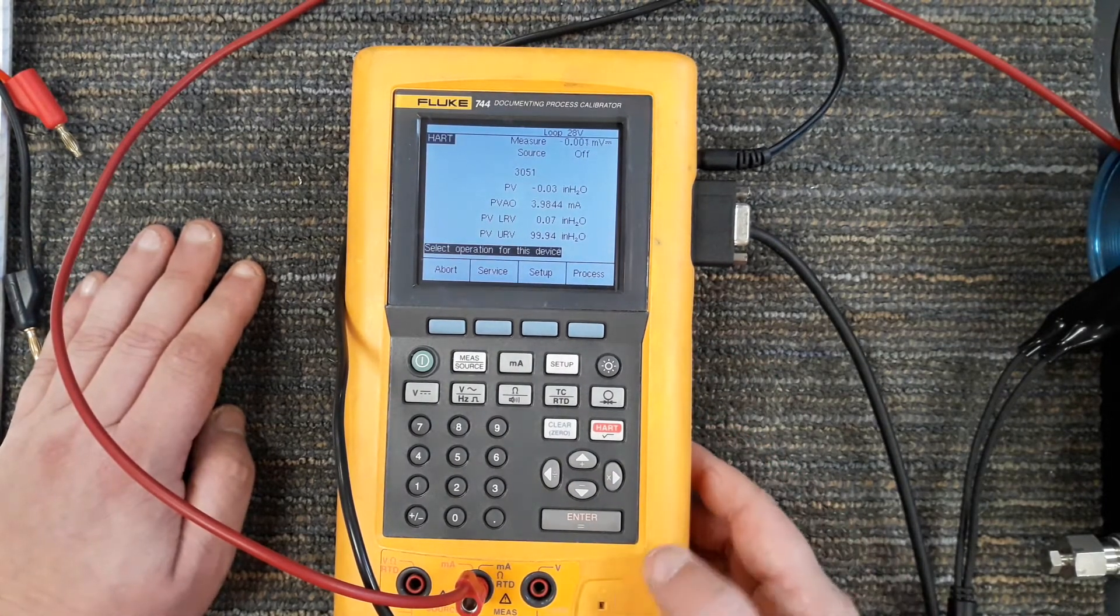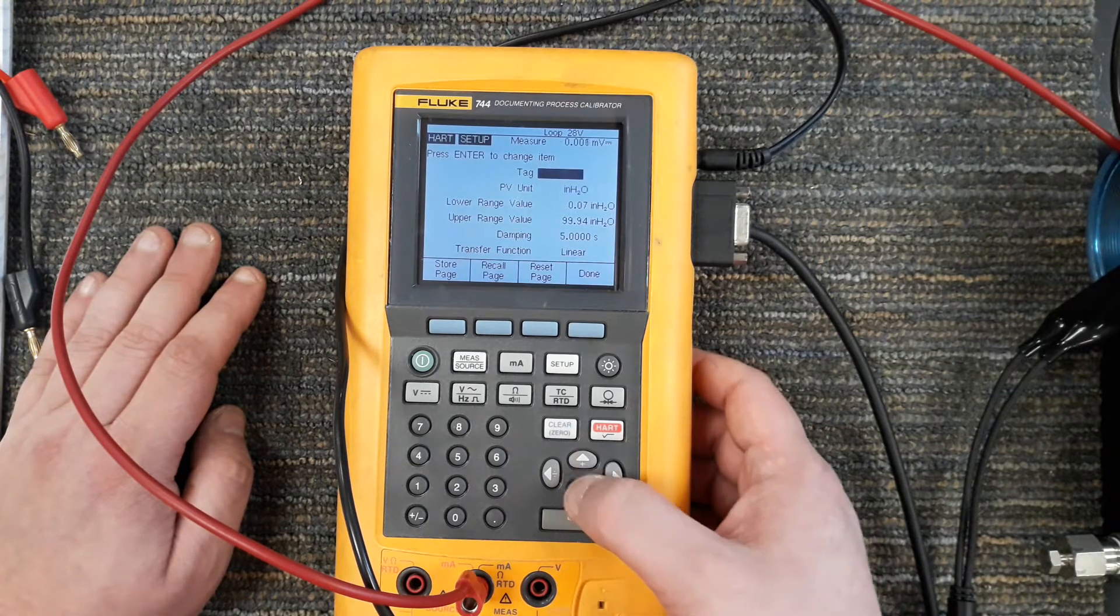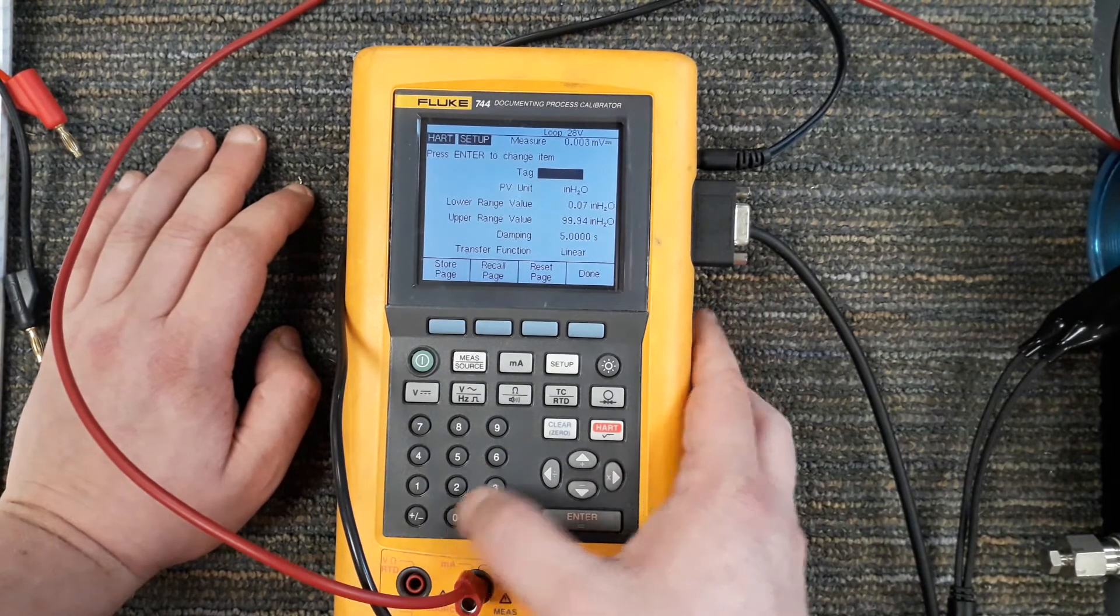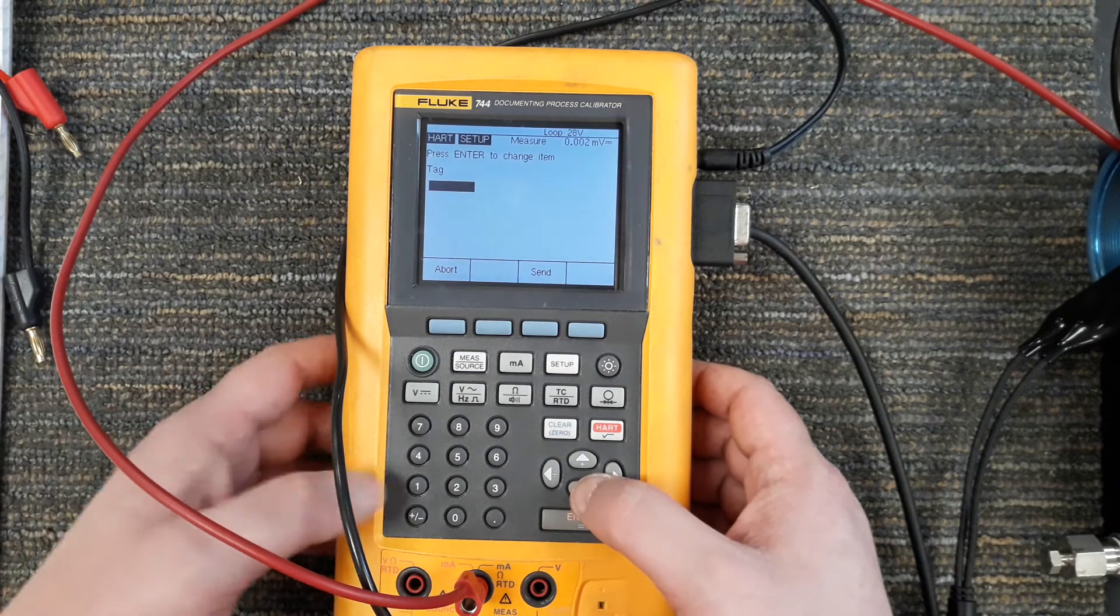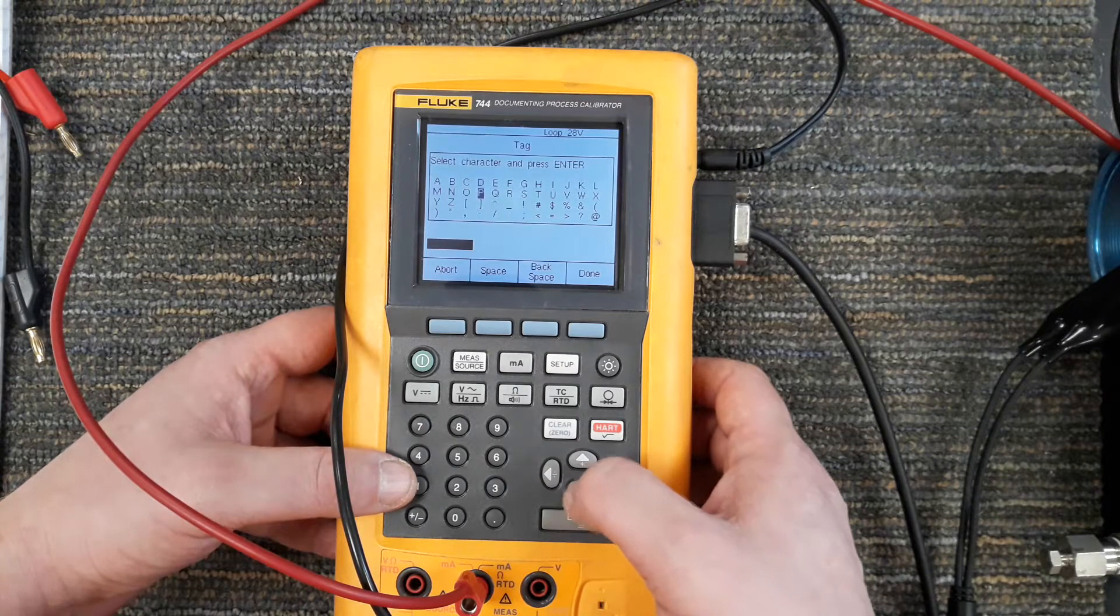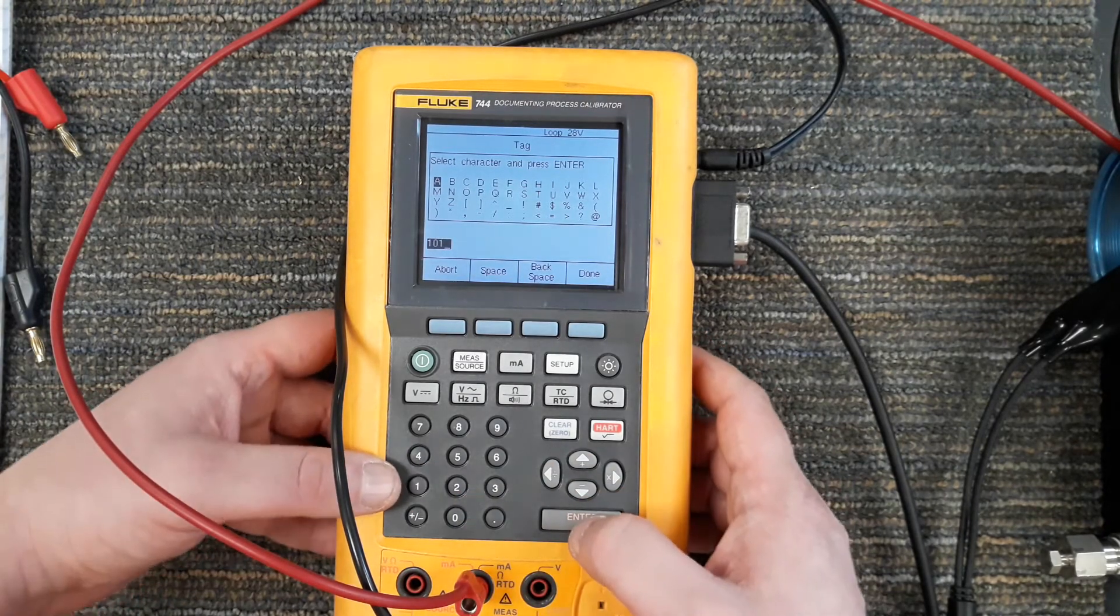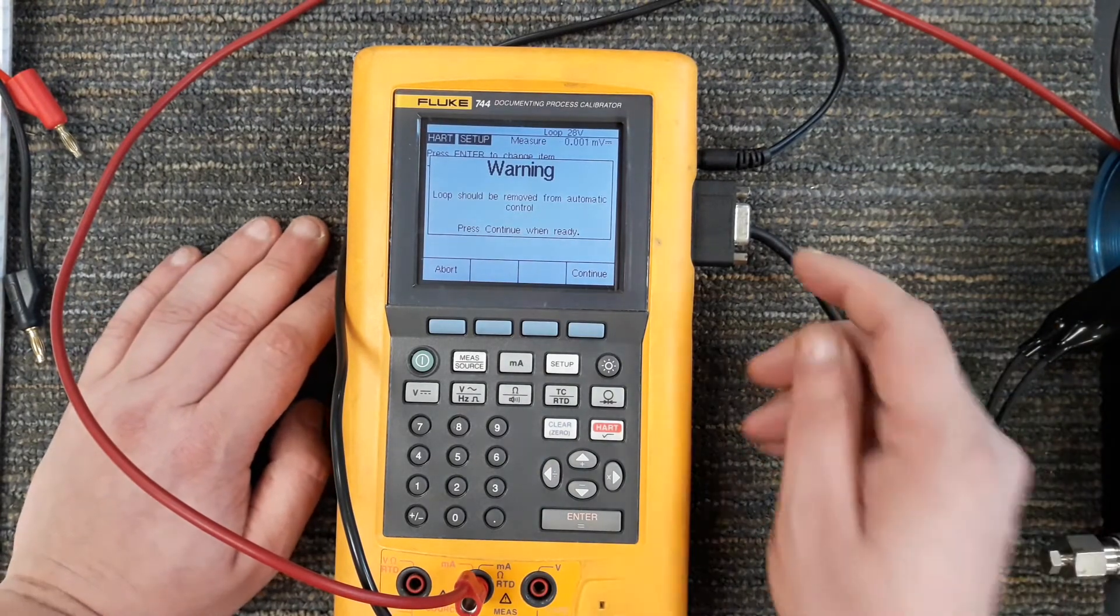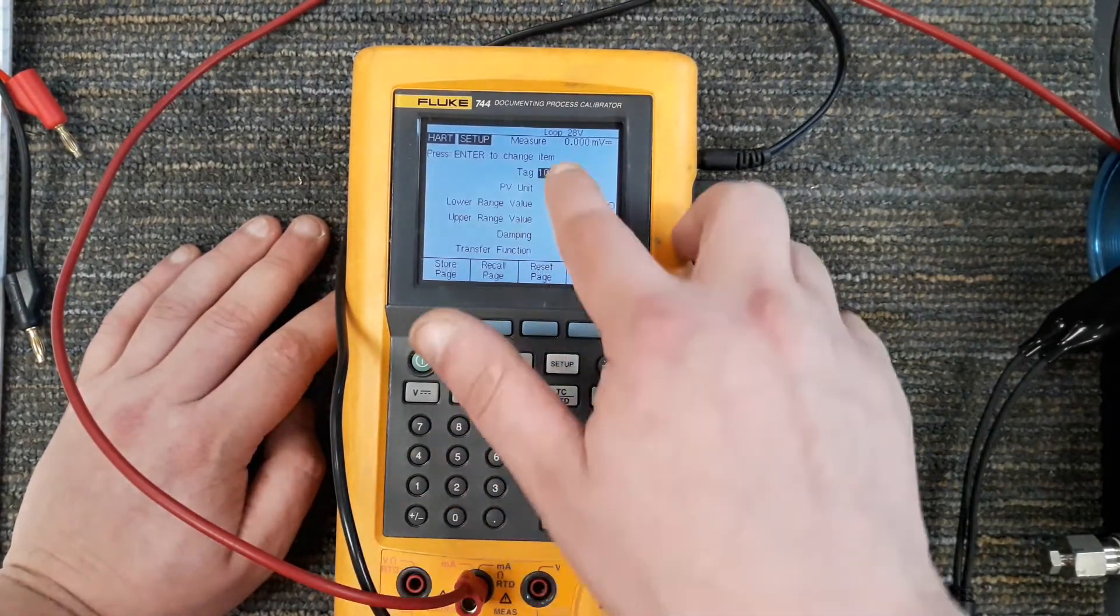If I go into setup, I can do basic setup and I can go in here and change the tag number for this. Say this is pressure transmitter 101. I have to actually go into here and give the tag number 101. Then I can send that to the transmitter. Loop should be removed from automatic control, continue. Now it has a tag number of 101.